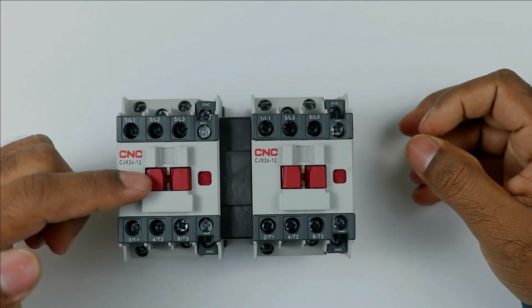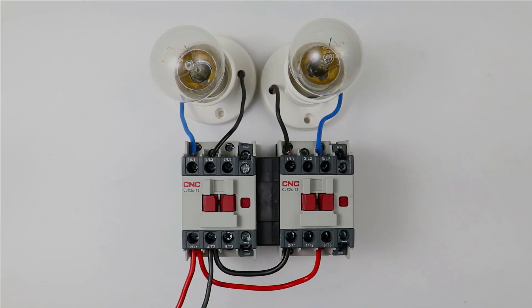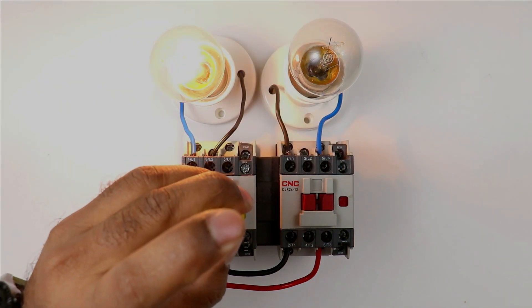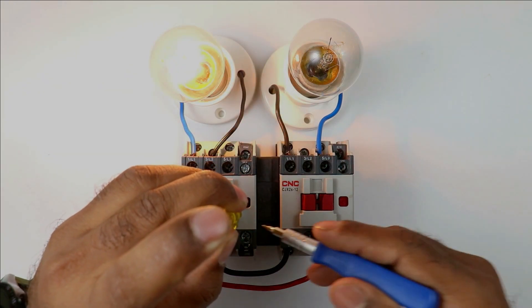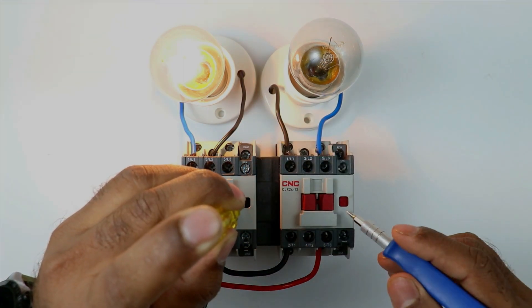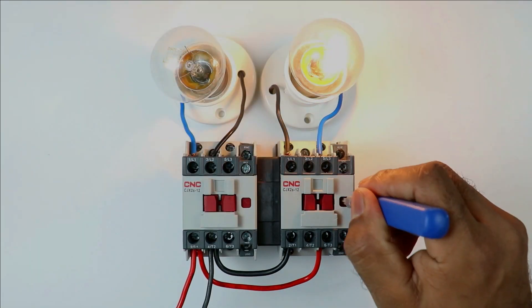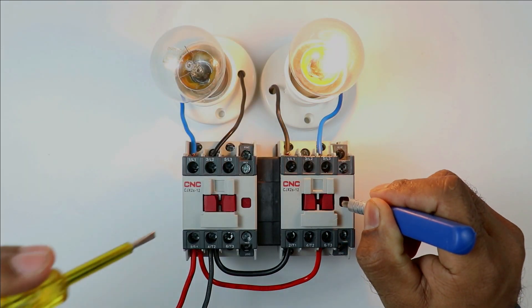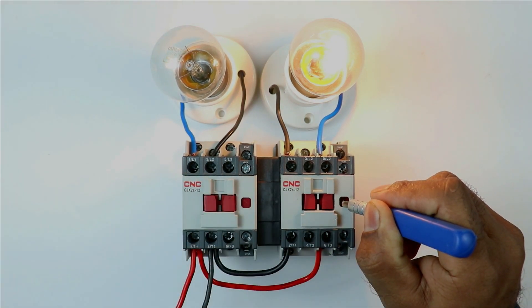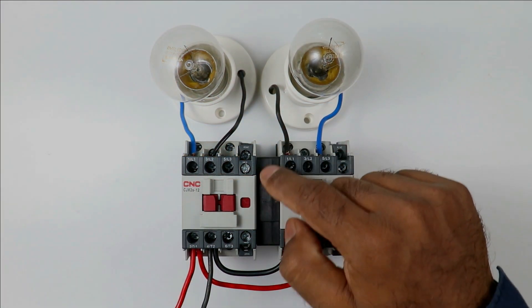For now, I am connecting a lamp with these contactors, so that you can clearly understand. Now first, I am turning on this contactor. I am directly turning this on, but you must perform electrical connection. This contactor is on now. You can see this lamp is in on condition. If I try to turn on this contactor, you can see it is locked and the lamp is not glowing. If I turn on this contactor and after that, when I try to turn on this one, you can see it is locked. You can say that we interlocked these contactors and precisely we done the mechanical interlocking.